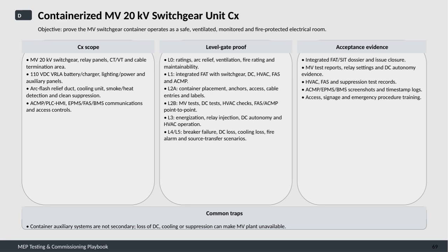Regarding the level gate proofs, we have several stages that verify different aspects of the installation. Level 0 covers the ratings, arc relief, ventilation, fire rating, and maintainability. Level 1 involves an integrated factory acceptance test with all major components like switchgear, DC power, HVAC, fire alarm, and control modules.